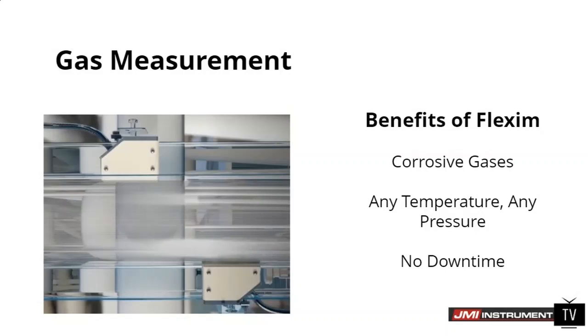And no downtime. That's the benefit of being outside the pipe as well. If you've ever had a demo or seen a demo done, you can do this without anybody even knowing that you're on the pipe because there's no process interruption. You don't have to do anything special to get a measurement. You just basically have to get on the pipe. And no downtime for installations. Basically, the installed cost for a Flexim meter is a tiny amount compared to an intrusive meter because we don't have to do really anything except run power and wiring to the meter.